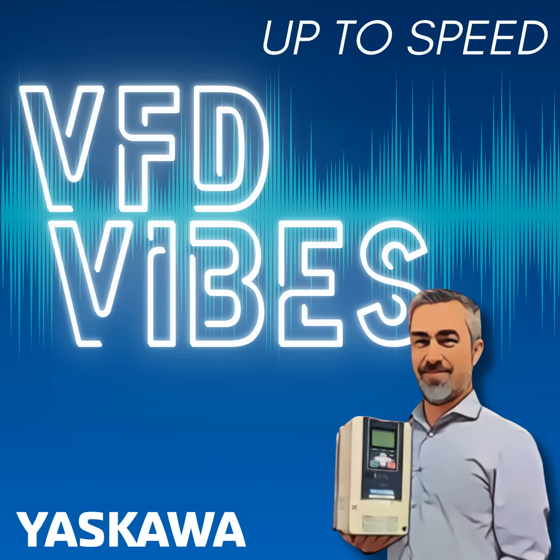But you already mentioned it's a little bit more stringent. So if you have an existing product that's certified under UL 508C, does it automatically meet the new standard, the 5-1, or does it need to be recertified? Yeah, UL won't just say, hey, this was a 508C product, therefore it can be a 5-1 product. They won't do that. So we have to do the work, retest per the new standard. Now, that doesn't mean any changes to the product whatsoever. There could be cases where we decide to do something different, but usually not. The new products that are certified to 5-1 aren't necessarily any safer than the existing products that are 508C. It's just that we had to test them by the new method.